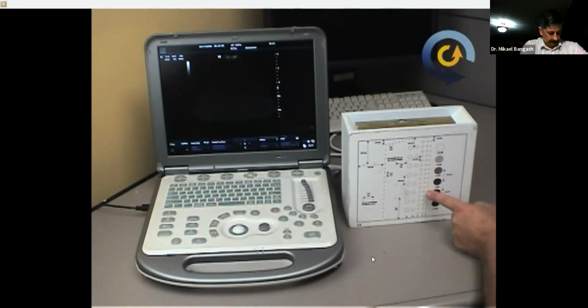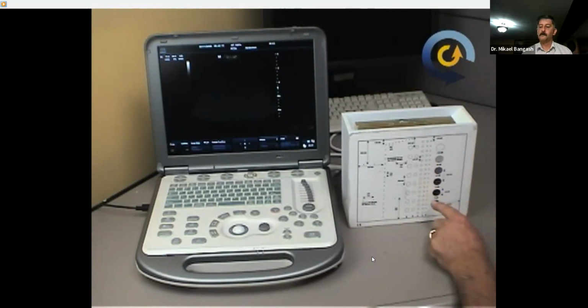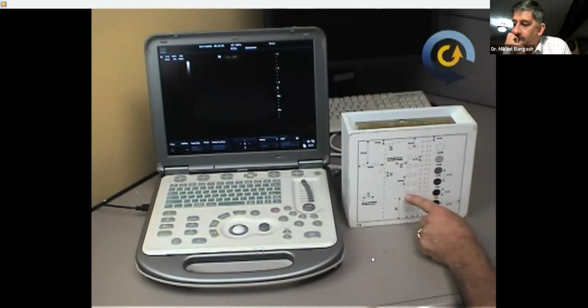These are the same size, these represent cysts, and these are hollow plexiglass rods again, and they're clear as you look at them with the ultrasound. So what you're trying to do is find out how small of an object you can still see the difference in the contrast between the surrounding tissue and, say, a cyst, and you also want to make sure that that cyst is clear. It doesn't have a lot of echoes in it, and that's what each one of these are for.